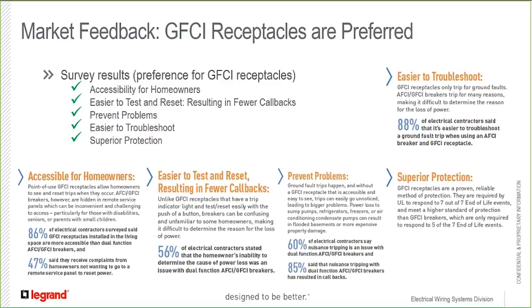Now, when we compiled this market feedback, basically what we found was that GFCI receptacles are still the preferred choice amongst electricians and contractors. I'll go over some of the survey results. The number one thing was the accessibility for homeowners. Point of use GFCI receptacles allow homeowners to see and reset trips when they occur. AFCI, GFCI circuit breakers are often hidden in remote service panels, which can be inconvenient and challenging to access.